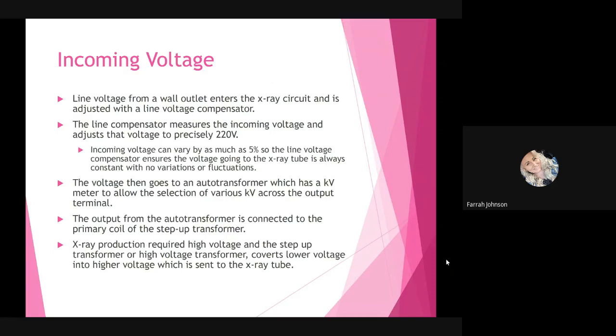Know that the incoming voltage can vary by as much as 5%. So the line voltage compensator is really important because it ensures the voltage going to the X-ray tube is always constant with no variations or fluctuations. Now the voltage then is going to go to the auto transformer, which is the first portion of your X-ray circuit. The auto transformer is going to have a kV meter, which allows the selection of various kVps across the output terminal. The output from the auto transformer is then connected to the primary coil of the step-up transformer, which is then going to move into our high voltage section of the circuit. X-ray production requires high voltage, and the step-up transformer or high voltage transformer helps convert that lower voltage into higher voltage, which is then sent to the X-ray tube.